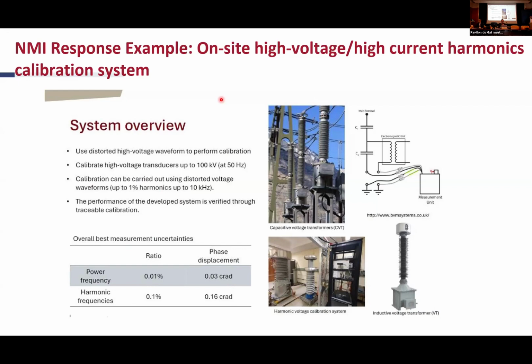So one example of how an NMI reacts to this is a system that we developed in Australia to calibrate voltage and current transducers with arbitrary waveforms that contain a fundamental and also harmonics up to 10 kilohertz. So we can generate, say, 100 kilovolts, 50 hertz in Australia, plus we can also add 1 kilovolt of harmonics. Or we can generate 4 kiloamps of 50 hertz and add 1 kiloamp of harmonics of our choice, of our client's choice, at up to 10 kilohertz.